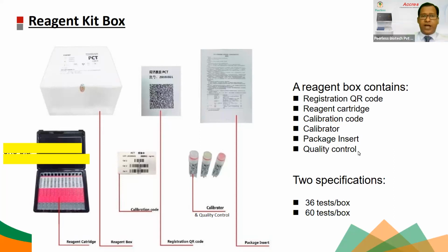To validate the calibration curve, we run 3 calibrators and match them with the master calibration curve. Once it is matched with the master calibration curve, the instrument will accept the original calibration curve or plot a slightly new calibration curve based on the master curve. And then further testing can be done. So this is the original protocol followed for calibration, and it is a very proper protocol, well evaluated. And then we are providing the quality control. If you want to run quality control to validate the assay, whether the calibration is fine and the results are fine, you can always run the quality control and see. We are providing it from our side. Whether you are going to do it or not is your customer's wish.